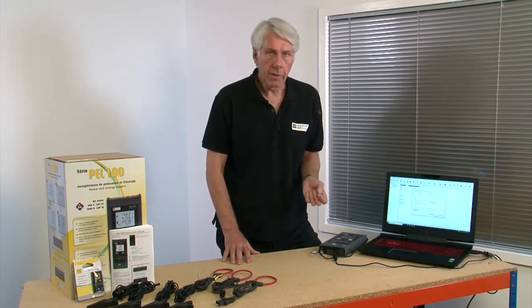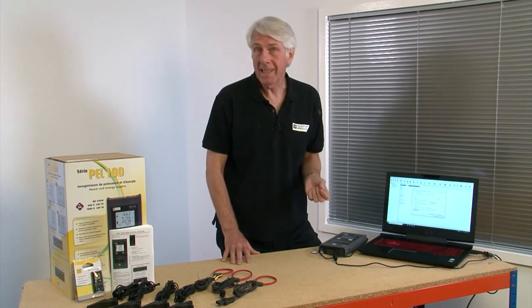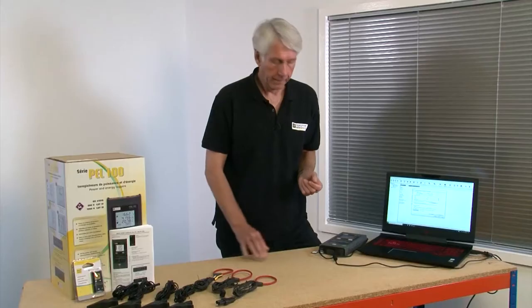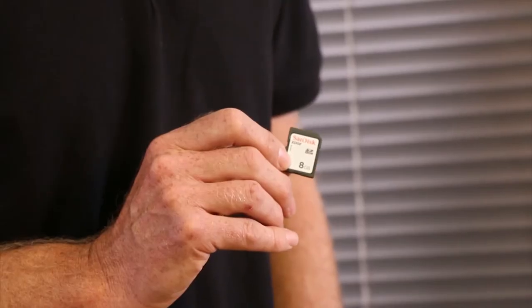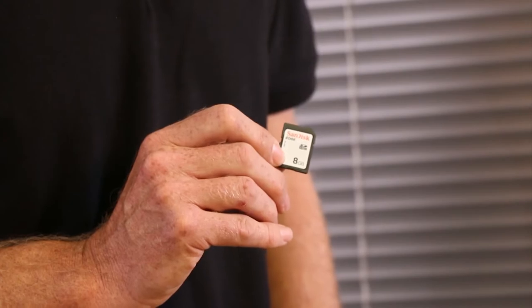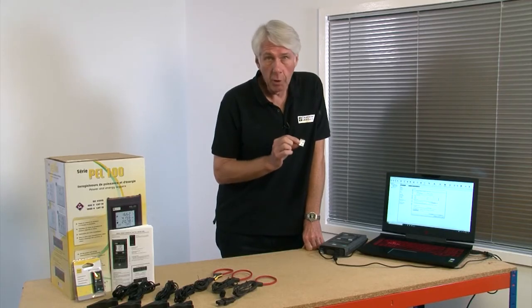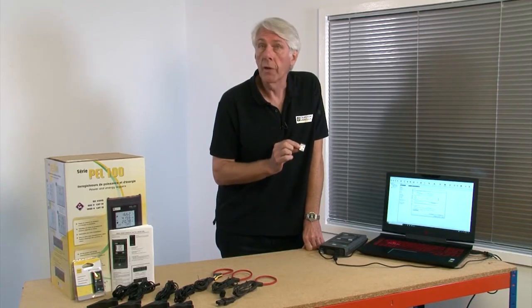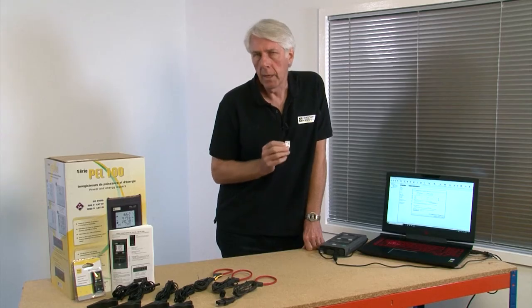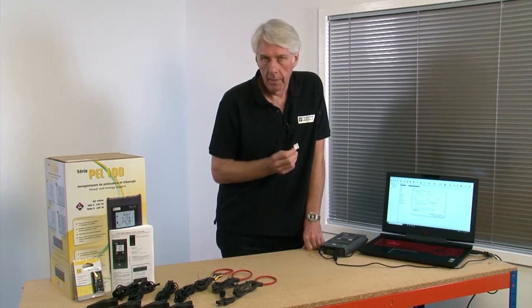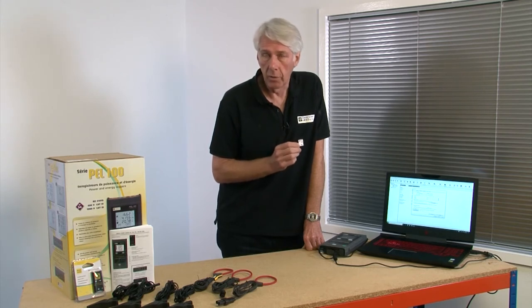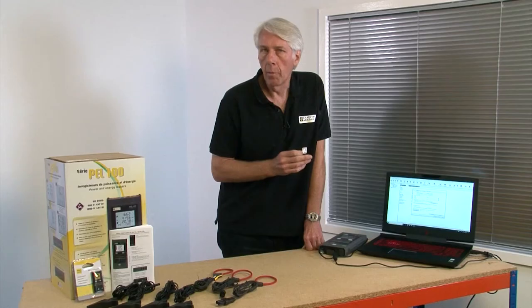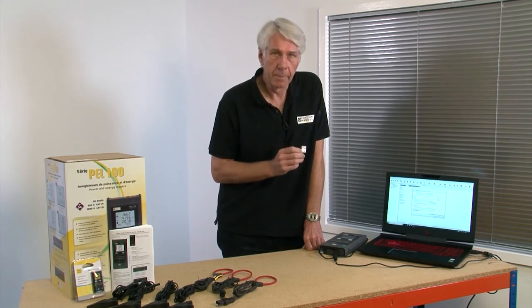If you move to a new installation it makes sense to reset the AGGREGATED MAX VALUES with the button shown here. So these values are not compromised by data from a previous installation. The PEL comes with an 8GB SD card which is more than enough for most instances and is already formatted. But if you change it for a new one make sure that it's formatted before use. A point to note here, SD cards degrade over a period of time. It's suggested that you change the SD card after every 30 or so recordings.